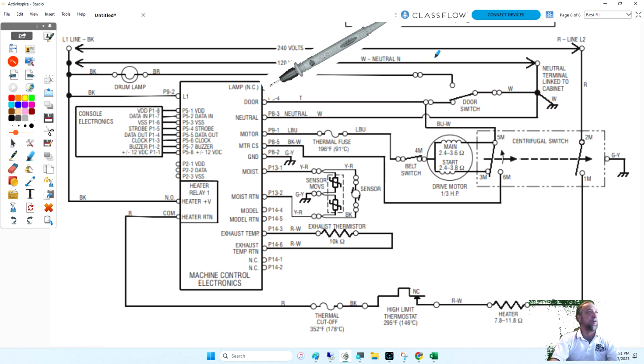Let me get my marker here. So this was power going to the motor here. We tested here for neutral, but what if this door switch was bad? Neutral would get this far. Would I get a 120 volt reading on my board at that point if that door switch was bad? No. Because if the door switch is bad, I will not get neutral.